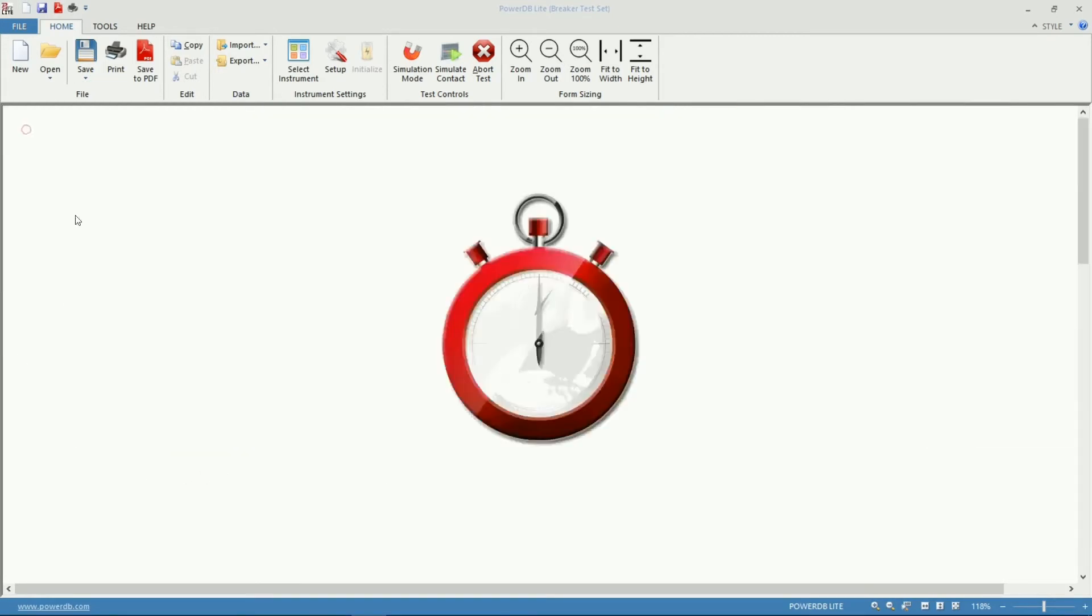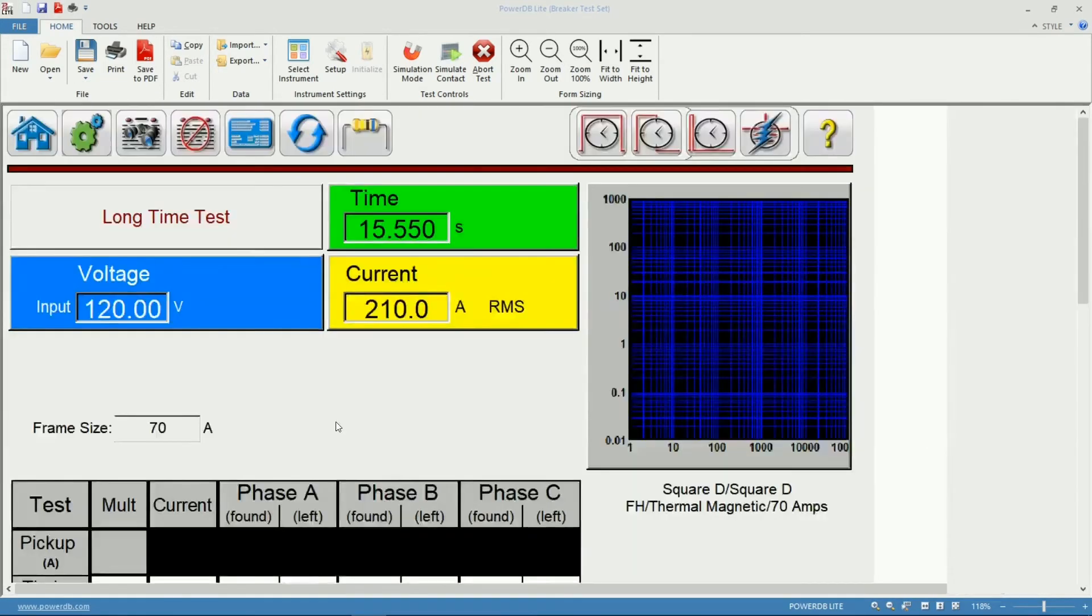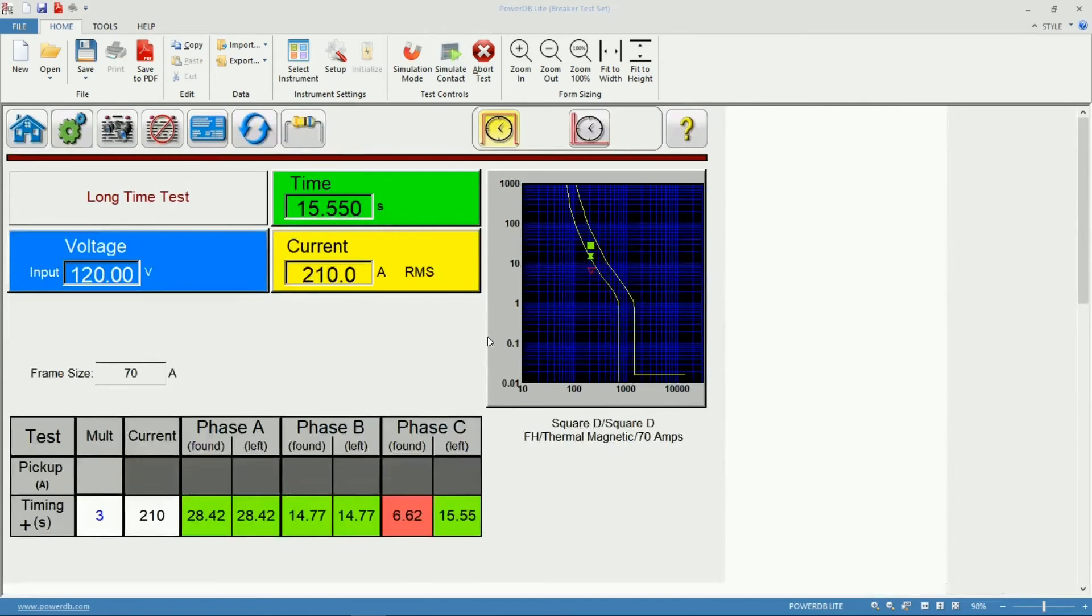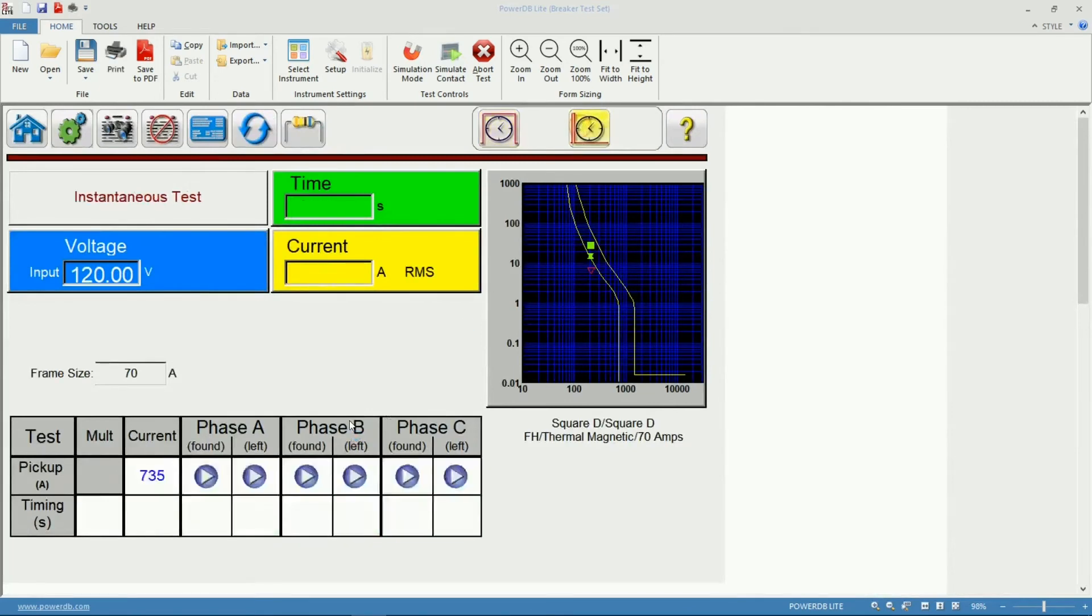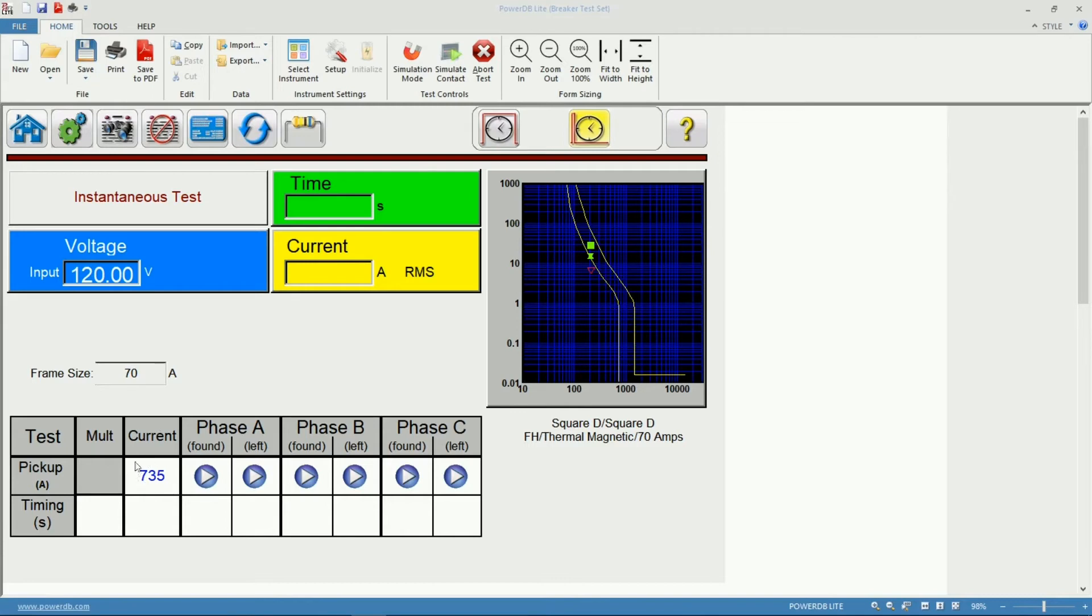I'll go back to my test screen to switch now to the instantaneous pickup. Again since we selected the breaker from our library, the software already calculated the current of the expected trip for this circuit breaker which is 735 amps.